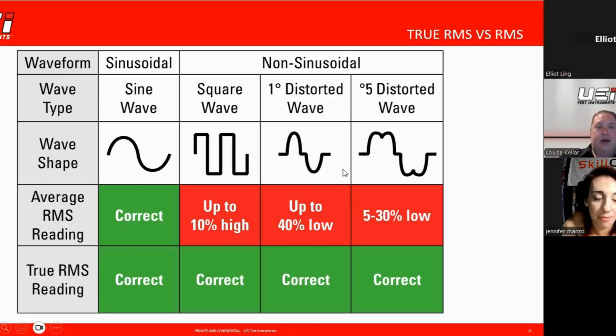I want to break this down a little since it's a lot to see on the screen. If we're working in a normal condition with no inverters, nothing, we'd expect to see a sine wave—a very consistent sine wave like on the left-hand side. An average sensing meter just takes a reading every so often, and it doesn't necessarily know if it's at the top, bottom, or middle of the peak, or if there was a weird distortion. It just takes all those readings and averages them out. So RMS is also synonymous with an average sensing meter.